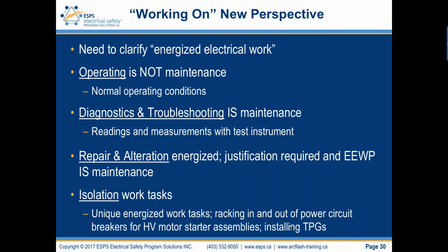Diagnostics and troubleshooting is maintenance. That's defined currently as working on in Z462 and 70E. Repair and alteration, energized, justified, requires an energized electrical work permit, is maintenance. Isolation work tasks are not maintenance. They are unique work tasks that are energized to put equipment into a safe working condition, or part of establishing an electrically safe work condition. These are acts of isolation, which is racking in or out power circuit breakers, which is not opening and closing. Racking in or out is physically removing a power circuit breaker in and out of a switchgear cell. And then installing temporary protective grounds is not energized electrical work. Those are work tasks related to isolation, right? And they will require arc flash and/or shock PPE related to them.